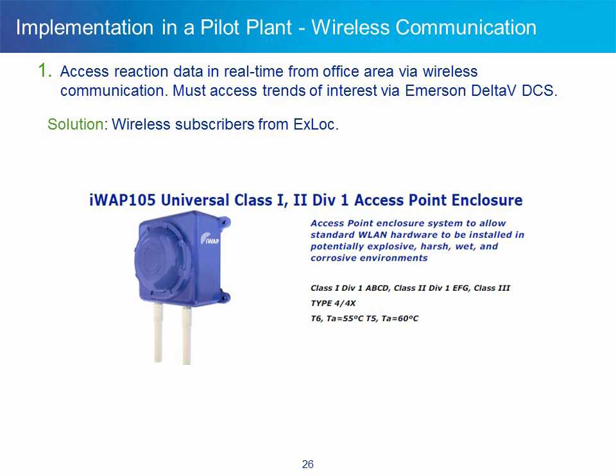The first requirement — that project engineers and chemists must have access to reaction data in real time from their office areas with wireless communication — was met using a wireless subscriber from ExLoc. The FTIR was connected to the wireless subscriber via duplex multimode fiber. The wireless subscriber communicates with wireless access points located in safe areas close to the pilot plants, enabling project chemists and engineers to view reaction data, spectra, trends, and spectra versus time surface plots from their offices. The wireless access point in turn sends trend data and instrument diagnostics to operators monitoring information through their distributed control system.